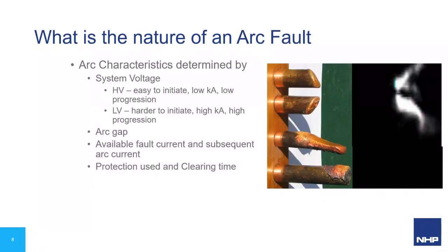So what's the nature of an arc fault? We do get these in high voltage and low voltage applications, so above 1,000 volts and below 1,000 volts. They have slightly different characteristics depending on the exact scenario. In high voltage, they're very easy to initiate. You're dealing with very high voltages, so it's much easier for that arc to be generated across a further distance. But you are talking about lower actual fault current levels, and that progression doesn't seem to happen as much. In low voltage, it's harder to initiate.